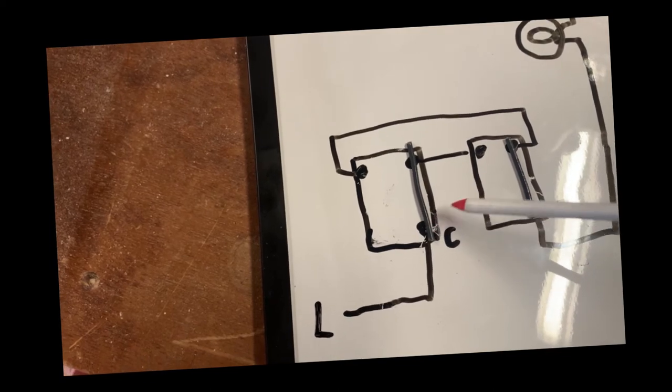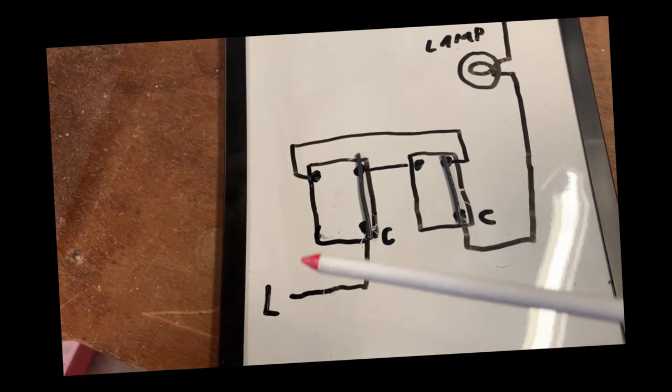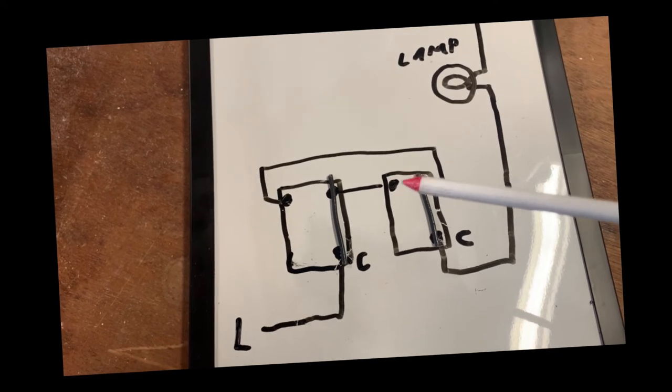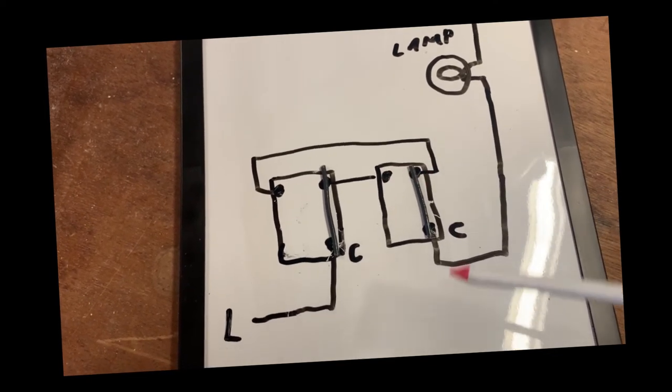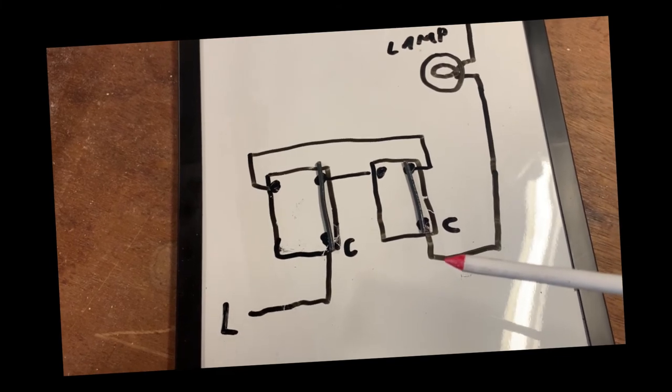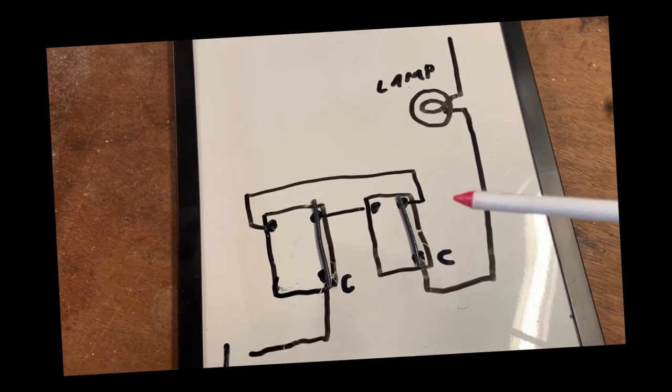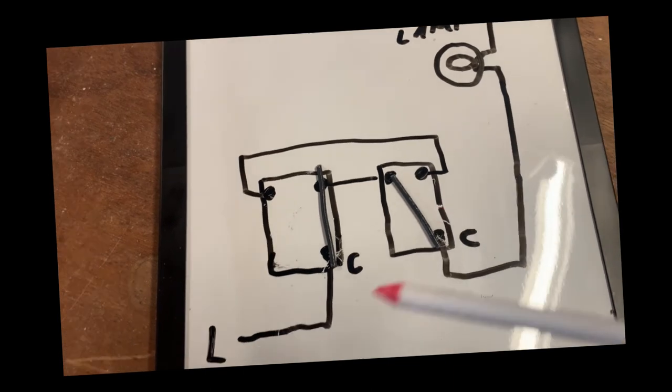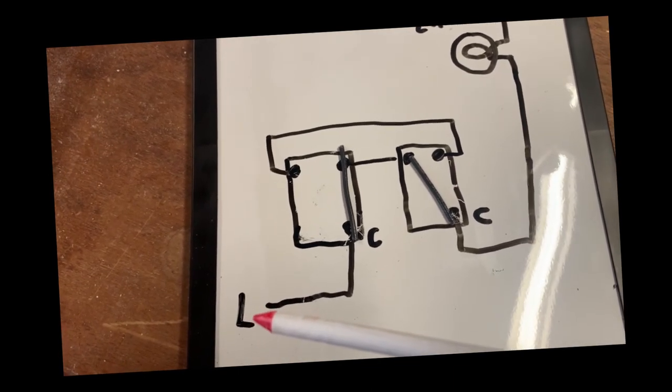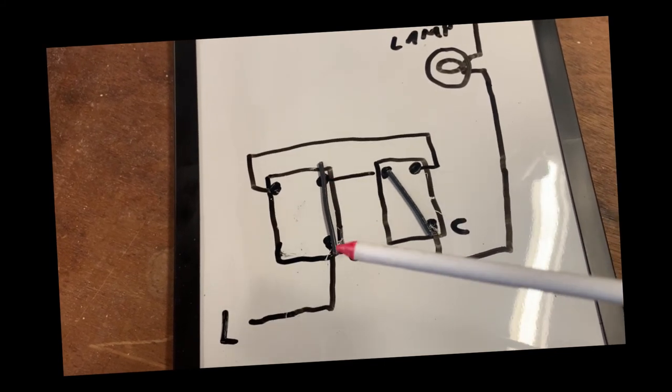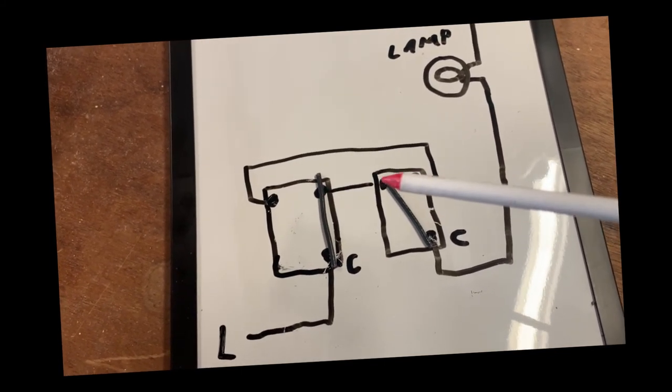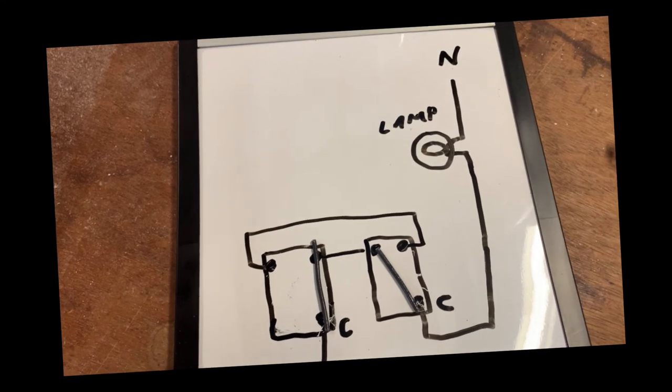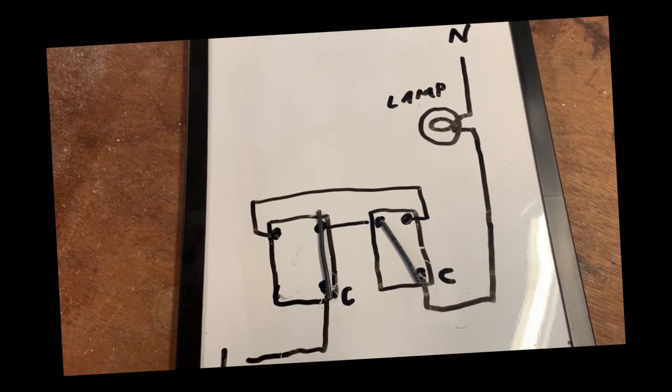I switch the switch and now let's look at the pathway for line. From line through that switch out this side to the second switch, and there's a break, so the light is not on. And then I run down the hallway again and want to turn the light on from that end. I go down there, flip the switch, and now the pathway from line or power into the switch, across those closed terminals, into the second switch down through common—voila, the light is on. That's how a three-way switch works, and that's our lesson for today.